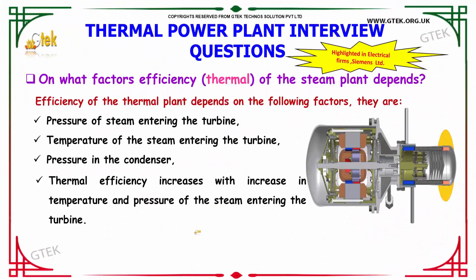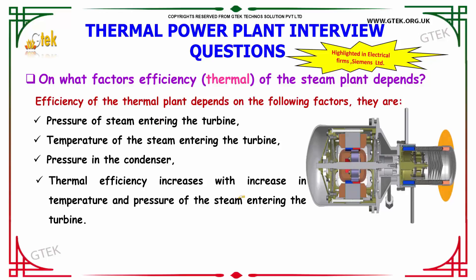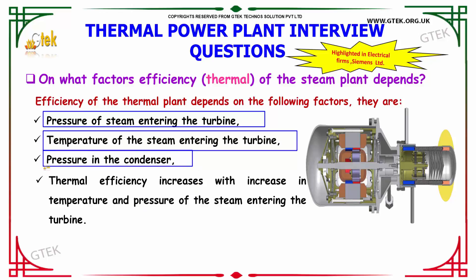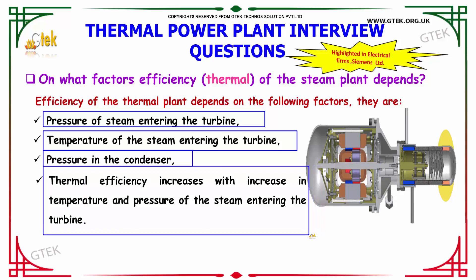On what factors does the thermal efficiency of the steam power plant depend? The efficiency of the thermal plant depends on the following factors: the pressure of steam entering the turbine, the temperature of steam entering the turbine, the pressure in the condenser, and the thermal efficiency increases with an increase in temperature and pressure of the steam entering the turbine.